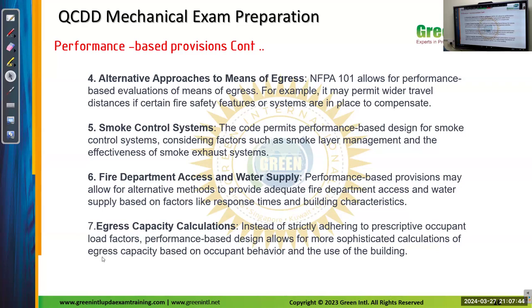What is the height from the floor to the smoke layer you have to maintain for the safe evacuation of the human. You cannot remove all the smoke together, but instead you can make it a layer. You will suck the smoke from different layers, which will not permit the smoke to come down. So there is a height requirement for each type. We will see it in our upcoming topics.